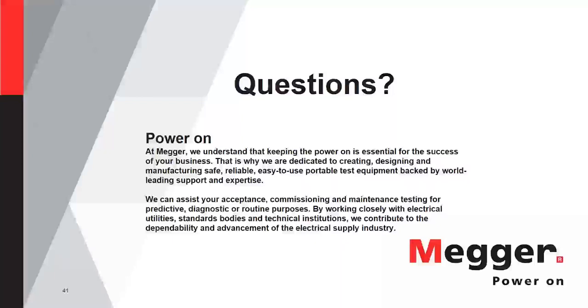Yes, those are the recommended starting values, and they are based upon our experience and on several things such as criticality. When we look at a flooded lead-acid VLA battery, because of the way they fail in a shorted mode, you can still get current through. IEEE will tell you 50 to 100% is a significant change in impedance that needs to be investigated. VRLA batteries fail in an open mode, so if you don't have a parallel string, you want to be cautious with them. Typically we're looking at 20 to 30% on those. IEEE will still tell you that a significant change is 50 to 100%.